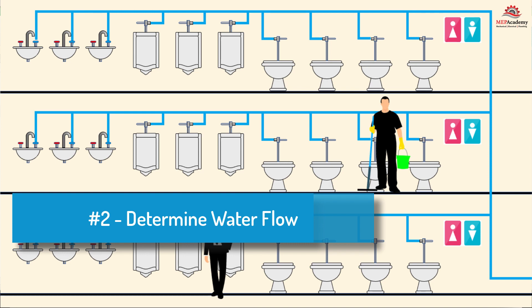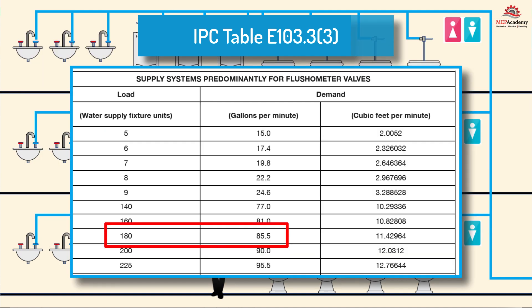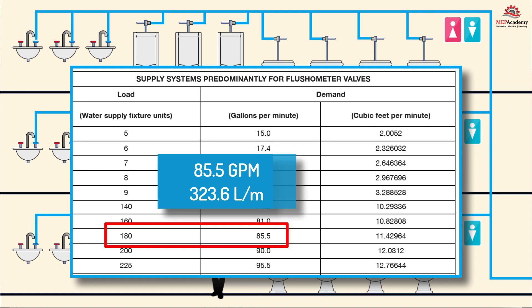Step 2: Determine the water flow in GPM or liters per minute. Determining the water flow involves finding the total water supply fixture units in the far-left column of IPC Table E103.3(3), then moving along that row to the intersection of the demand column for supply systems with flushometer valves. Our total of 178.5 fixture units is close enough to 180, so we use that row, giving us a water flow of 85.5 GPM or 323.6 liters per minute.